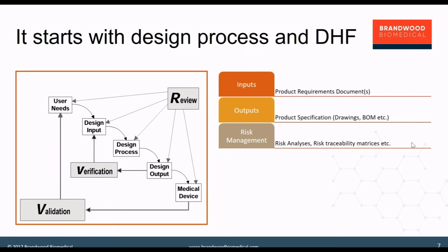So the risk management file would be essentially developed as part of the DHF implementation. It's important that traceability there be maintained such that all the impacts to the patient or the users of the product are considered, and relevant mitigations are implemented through the design. So essentially there is a relationship between the risk management file and your input requirements as well.